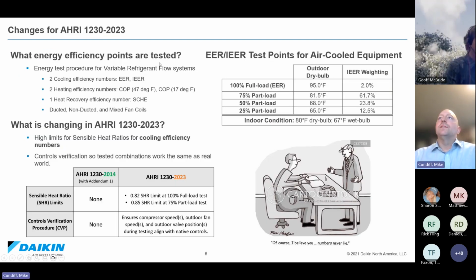Okay, so what energy efficiency points are tested? You still have those two cooling efficiency numbers, EER and IEER. You have two heating efficiency numbers, a COP at 47 and a COP at 17. You have a heat recovery efficiency number, the simultaneous cooling and heating efficiency right here. And again, that's for ducted, non-ducted, and mixed fan coils.